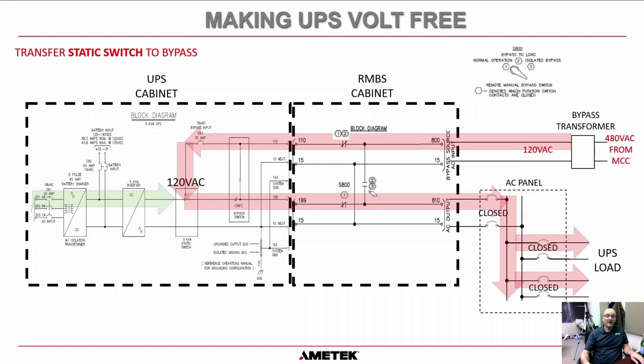Now, if we want to make this UPS volt free, the first thing we need to do is transfer the static switch to the bypass position. So you can see we have now pushed the bypass to load button on the front of the UPS, and power is now flowing from the bypass still through this contact. We're still in position 1, nothing has changed there, and we're now going through the static switch in the UPS. The inverter and the charger are still energized, but they're not supplying power anymore. The bypass is supplying the power to the load circuits. Okay? And there's a good reason why we always transfer a system to static bypass before we move the switch to position 2. And I'll explain that in just a moment.